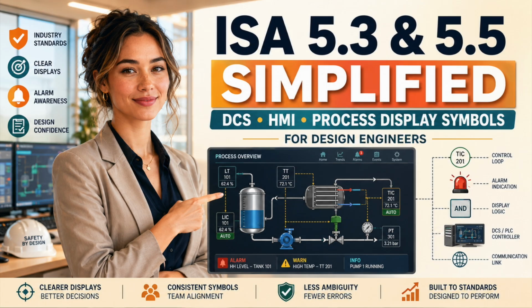Equipment state must be equally disciplined. Commanded state is not actual state. A start command does not prove that a motor is running. An open command does not prove that a valve has opened. A breaker close command does not prove electrical continuity. Where feedback exists, the displayed state should be based on feedback.